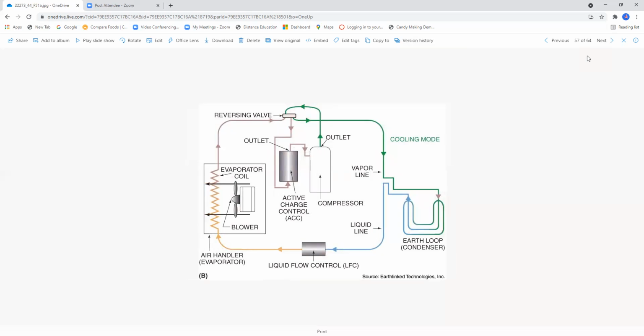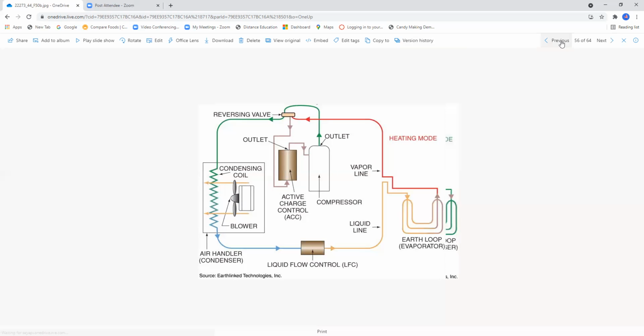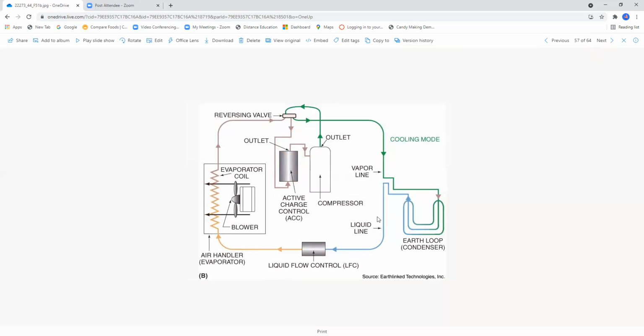Okay, in this one here, this is in the cooling mode, so it's a little bit different. Now the earth loop is the condenser, and if you remember in the previous slide, that was the evaporator. So now we just changed the function. Okay, and then of course got the liquid line, got the vapor line, the compressor, the outlet, the active charge control for this unit, and of course the reversing valve and the evaporator coil with the blower and all the other good components there.